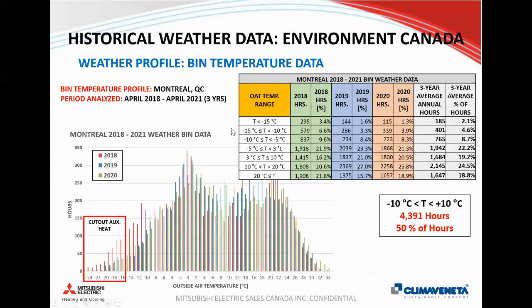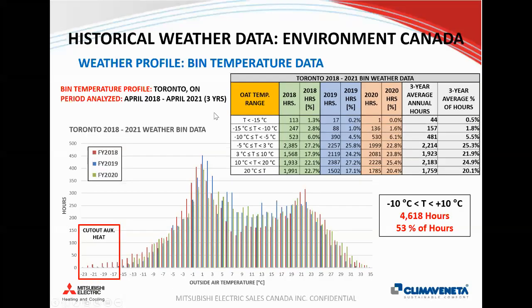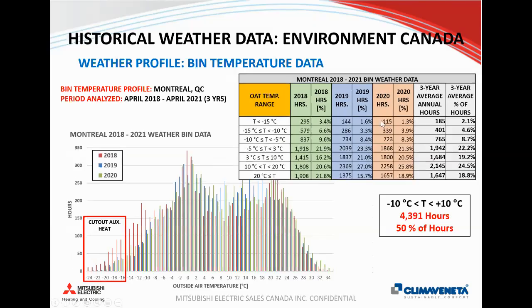Similarly, for Montreal, we're starting to get into a bit more harsher climates. Toronto, skipped over a slide here. Toronto, our design temperature is -23, but whenever you look at the actual number of hours where it goes below -15, it's only 44 hours. So even this past winter that we just had in Toronto, there was 1 hour where it was below -15, where you couldn't use some sort of heat pump technology.